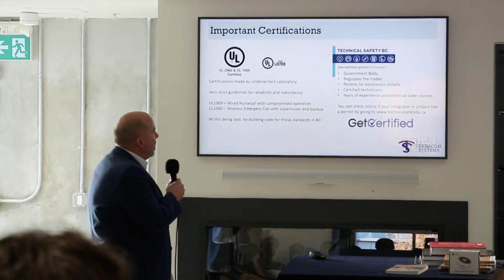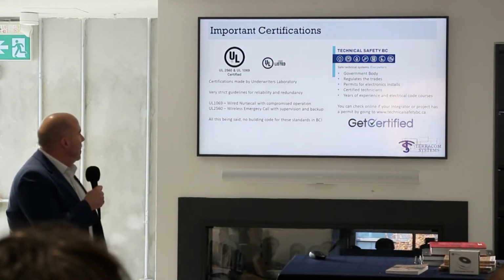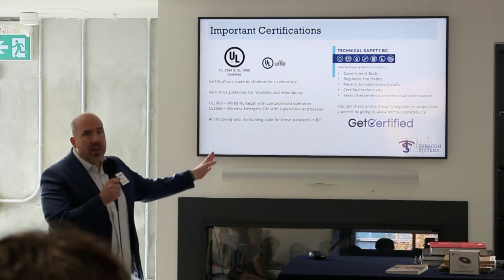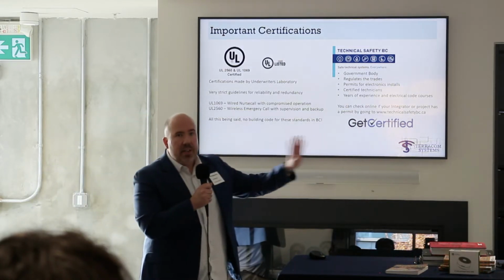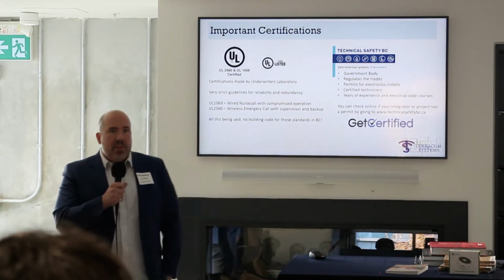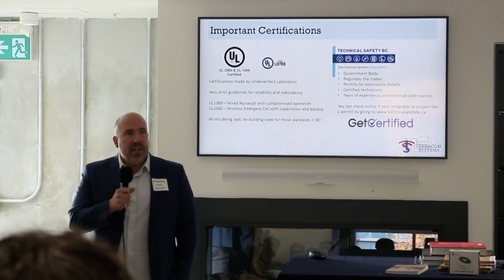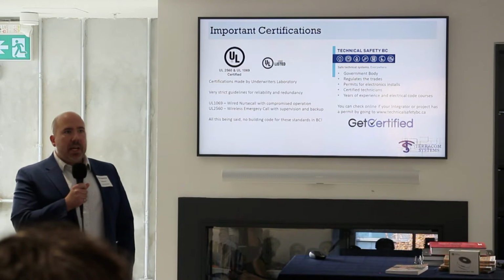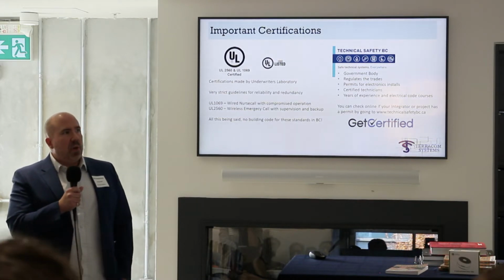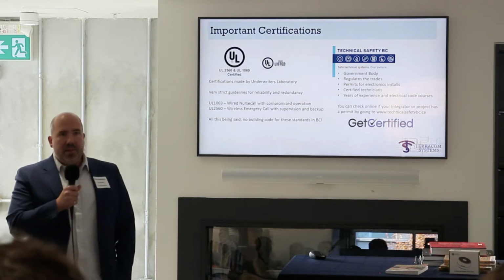So a couple of things I want to talk about with regards to certifications for systems nowadays. There are a couple of important things with regards to the product line you choose and the integrator you choose. One thing that's really nice is Underwriters Laboratories. I'm sure we've all heard of UL, ULC, if something's ULC listed. In the past few years, they've actually come up with standards for nurse call systems. So when it comes to something more hospital grade, long-term care, it's UL 1069 certified.